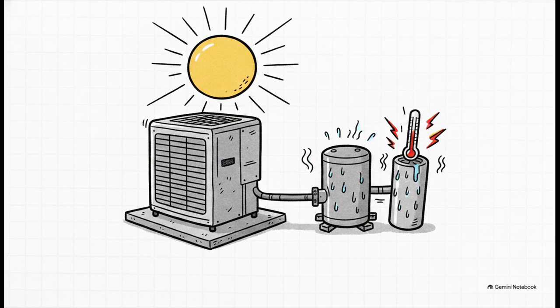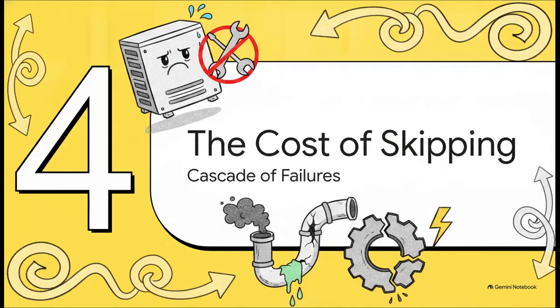That thing can run its internal components 10 to 15 degrees hotter than the exact same model sitting in a shaded yard over in La Jolla. That extreme inland heat load pushes the compressors so much harder, and it's the exact reason why capacitor failures show up way earlier on inland heat pumps. Now let's look at Section 4, the true cost of skipping.